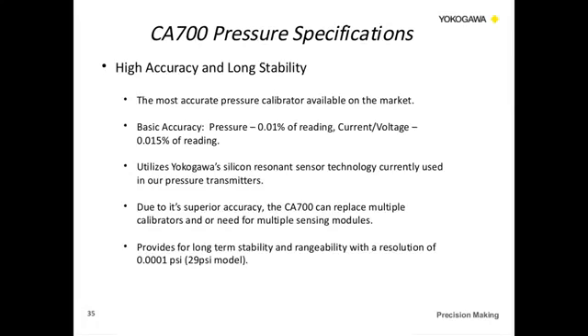The unit utilizes Yokogawa's silicon resonance sensor, a technology that's currently used in our pressure transmitters, and it's a proven type of technology. It's highly accurate and very stable over time, and it's been used in many harsh environments. So it's a very well performing and long-lasting technology. Due to its superior accuracy, and we talked about this with external modules, you can do a lot with one module that you would need multiple modules from another manufacturer for. In addition, it also provides a lot of rangeability. You're able to resolve down to 0.0001 PSI.